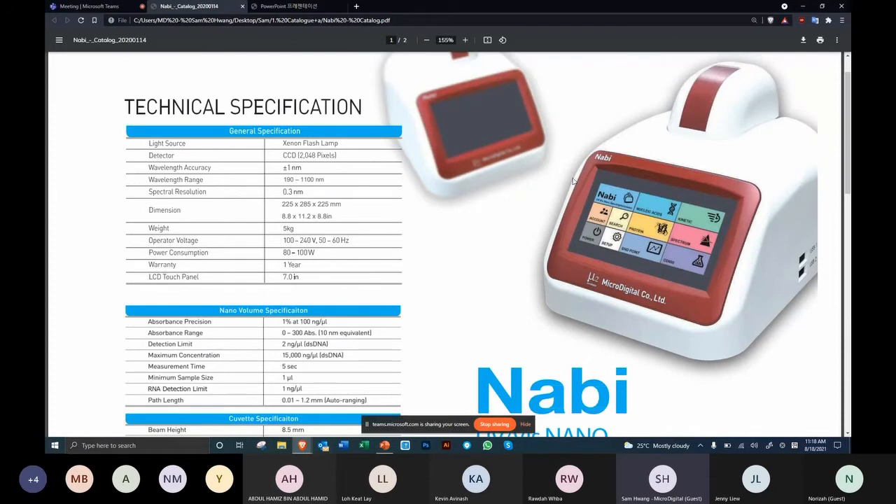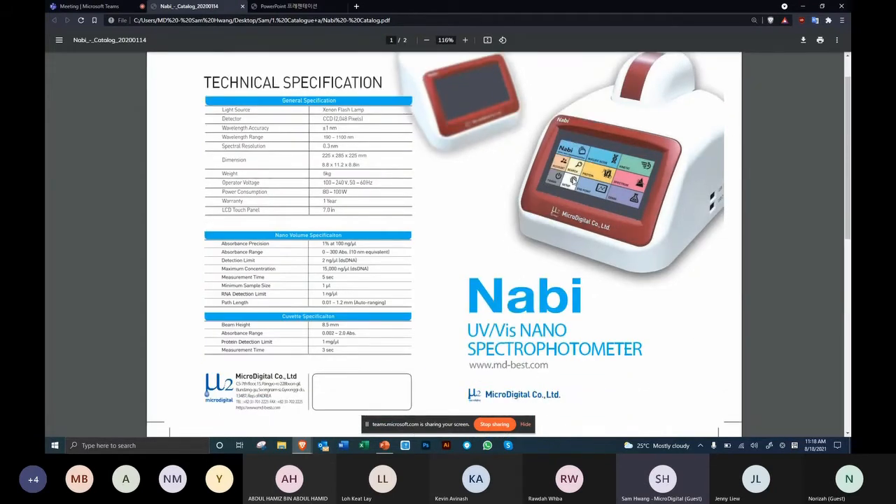So this is our Nabi UV-Vis nano-spectrophotometer. The light source is a xenon flash lamp with a lifetime of up to 60 million measurements — which by our estimate should last at least seven years. Our detector is a CCD with 2,048 pixels. Wavelength accuracy is plus or minus one nanometer. Wavelength range is 190 to 1,100 nanometers. Spectral resolution is 0.3 nanometers.